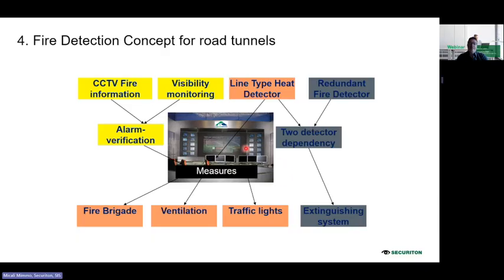People normally operate the system, but when there is a fire alarm, the triggering normally follows an automatic sequence, so it does not depend on an operator. The operator can also trigger all these kinds of equipment, especially the ventilation and the traffic light. But this is also fully and automatically integrated in case this does not happen.